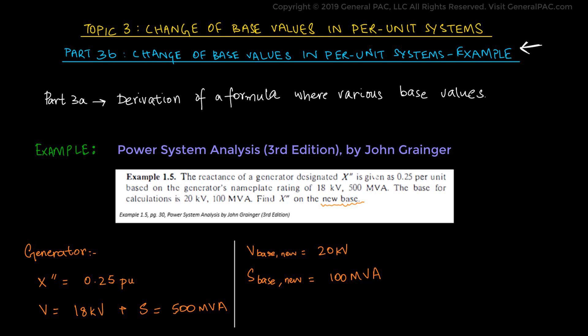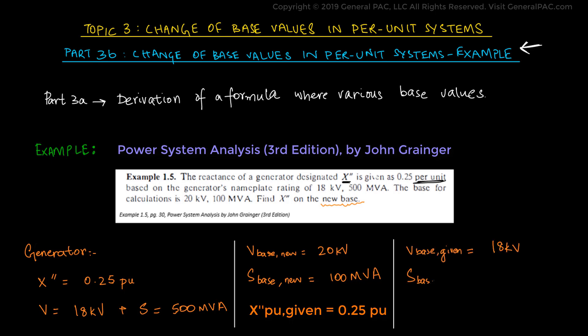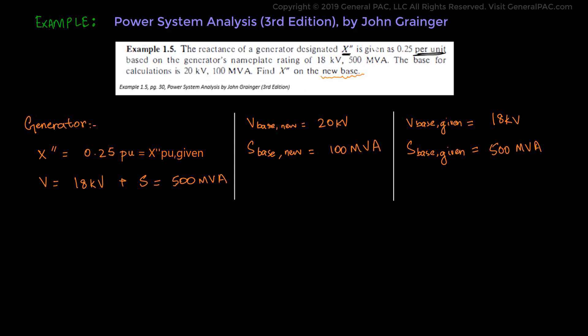We can see that the reactance X double prime is specified in per units. We can understand that this per unit value, X double prime per unit given, is equal to 0.25 per unit. We also know that the rating of the generator given are taken from the base value as we learned in the earlier topics of this series. So the given X double prime value is calculated using the given base values: V base given equals 18 kV and S base given equals 500 MVA. To calculate the new value of X double prime in per units, we use the formula derived in Part 3a.